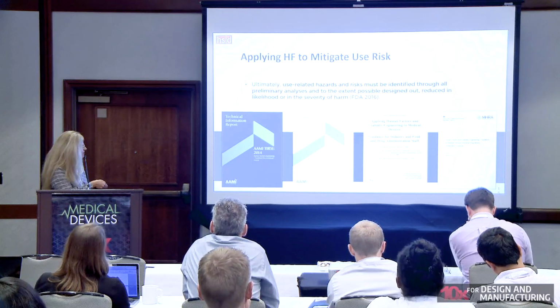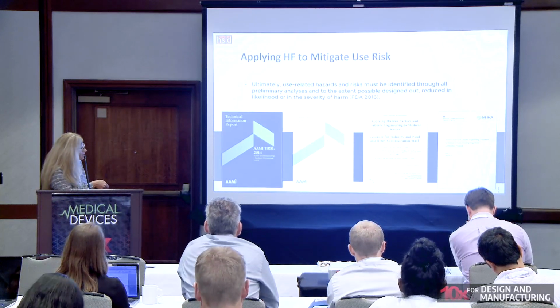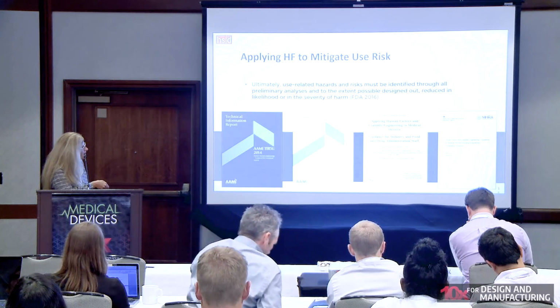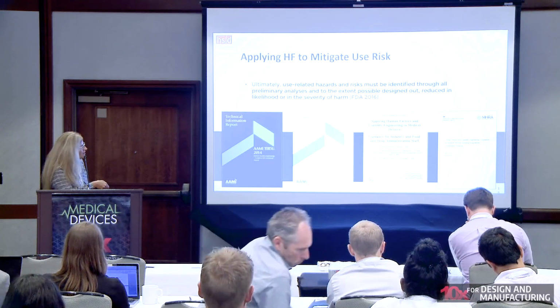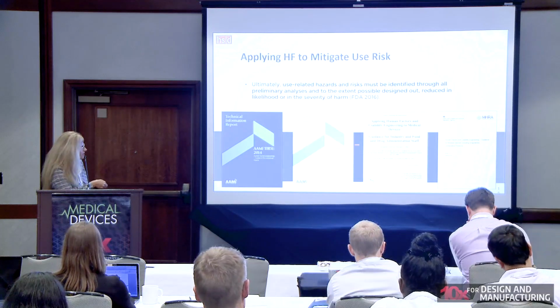And then historically, this document here, which is from MHRA, is from the UK, and it talks specifically about the usability in combination products. And the difference between this document and these other two is a greater emphasis on instructions for use. And with that, that means that part of the user interface as defined by the regulatory agencies are the overall design, the graphic user input, the instructions that are given to the user, everything that would be available to them upon market release.